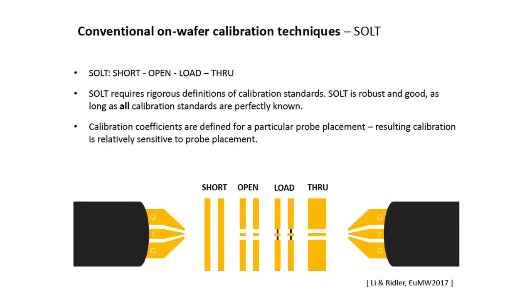I will now review a few conventional calibration techniques. The first one is SOLT — Short, Open, Load, and Through. SOLT requires a rigorous definition of calibration standards, so you need to know the electrical behavior of all these standards very well. If you know that, SOLT is very robust and very good. However, sometimes you don't know that. Also note that calibration coefficients are defined for particular probe placement, meaning SOLT calibration is relatively sensitive to probe placement errors — if your probes shift slightly forward or backward during measurement compared to calibration, you will have more errors.